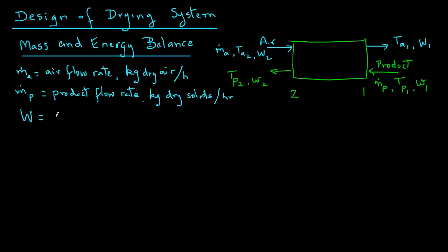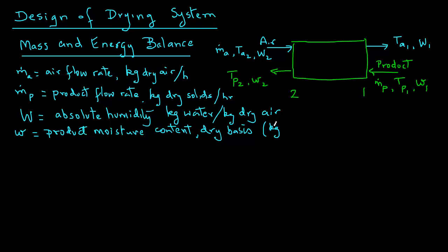Capital W is the absolute humidity. If you remember from psychrometrics, it's also called humidity ratio or specific humidity, and it is kilograms of water per kilogram of dry air. Small letter w is the product moisture content on a dry basis, and the units will be kilograms of water per kilogram of dry solids.